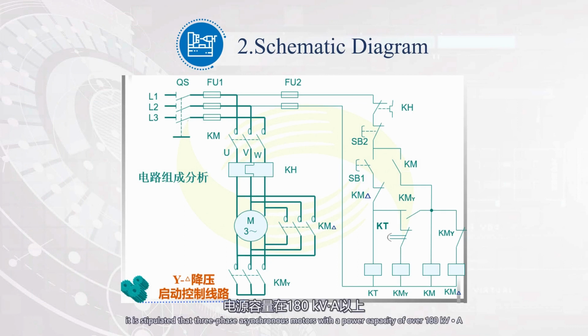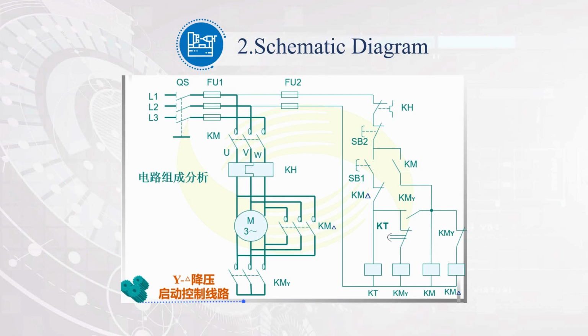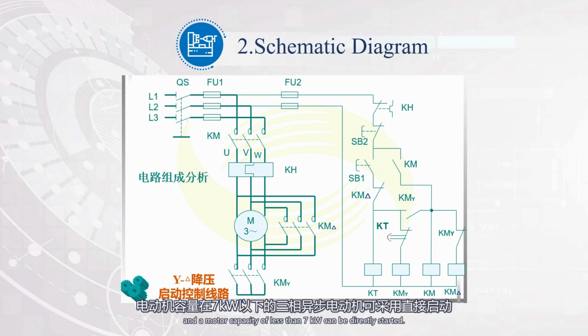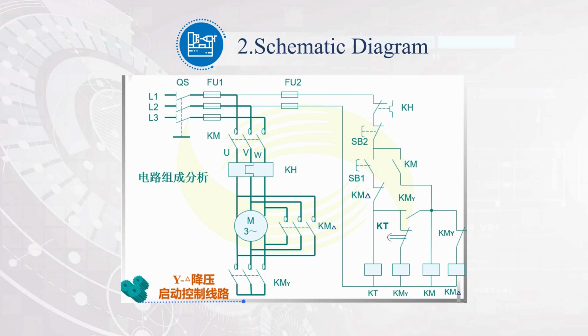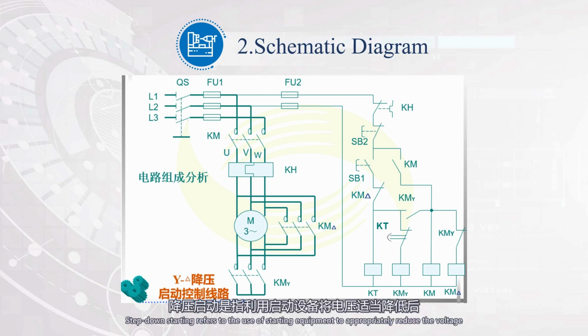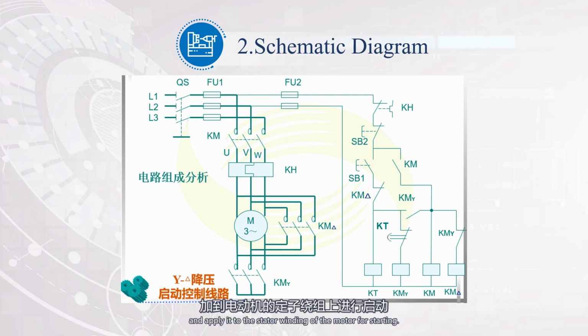Usually, it is stipulated that three-phase asynchronous motors with a power capacity of over 180 kVA and a motor capacity of less than 7 kilowatts can be directly started. For those that do not meet the conditions for direct starting, depressurization starting must be used. Step-down starting refers to the use of starting equipment to appropriately reduce the voltage and apply it to the stator winding of the motor for starting. After the motor starts and operates, the voltage is restored to the rated voltage for normal operation.